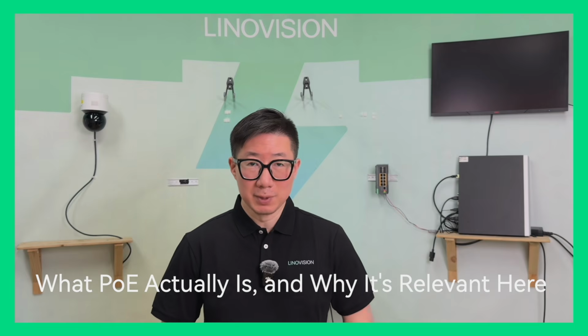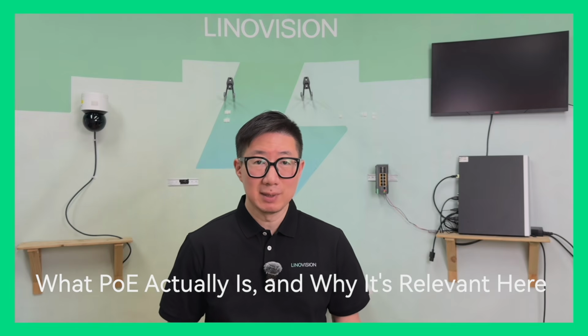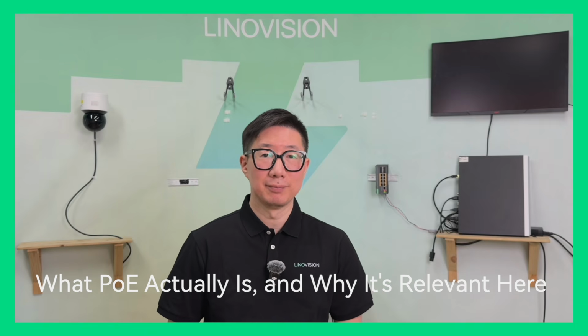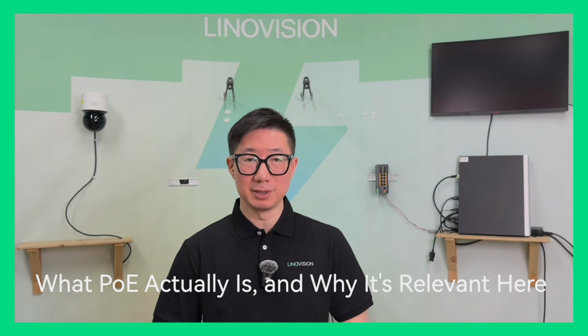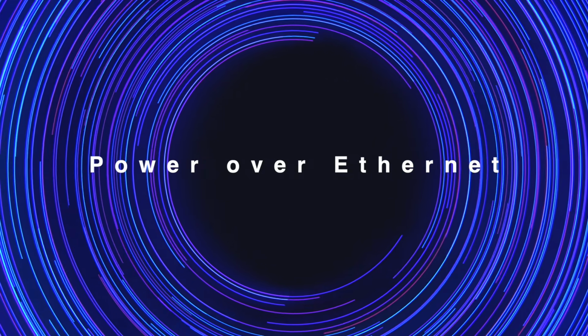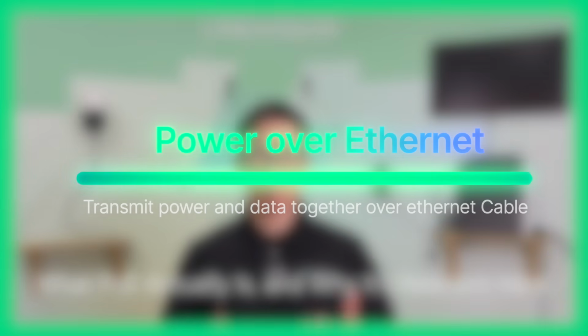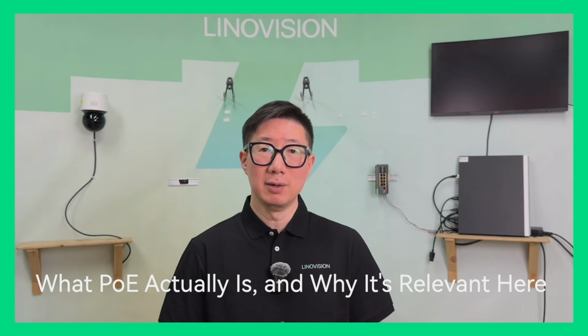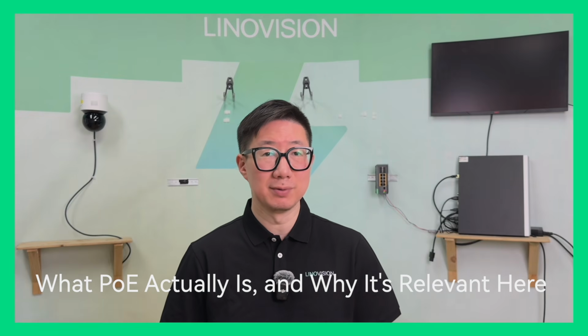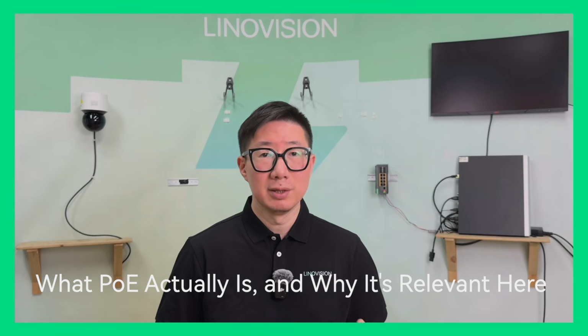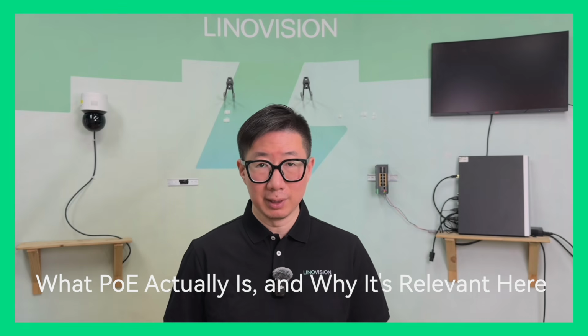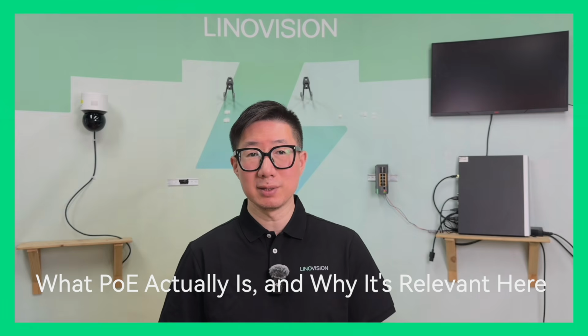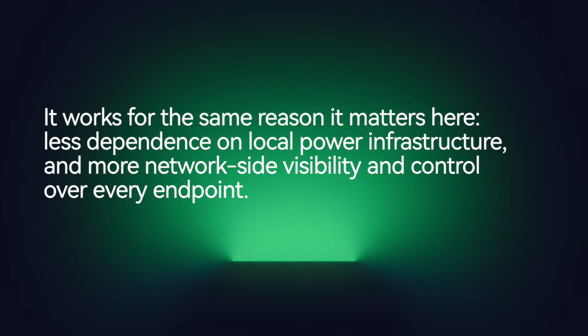For anyone who hasn't worked with PoE in a lighting context before, let's quickly establish what we're talking about, because the concept is easier to understand from the adjacent applications. PoE, Power over Ethernet, delivers both power and data over a single Ethernet cable. That model is already extremely well proven in IP cameras, wireless access points, VoIP phones, and access control readers. The reason it works so well in those applications is the same reason it's relevant here. It reduces dependency on local power infrastructure.